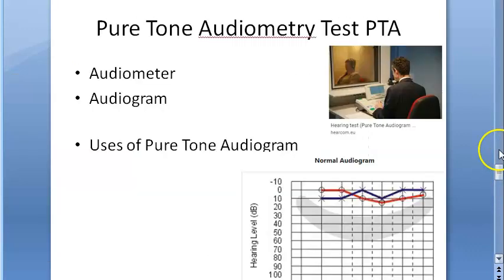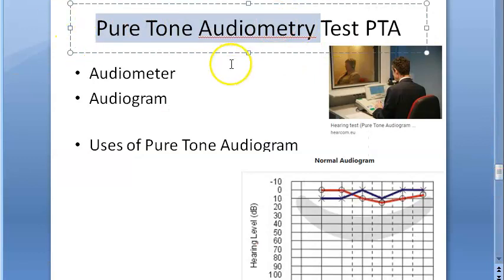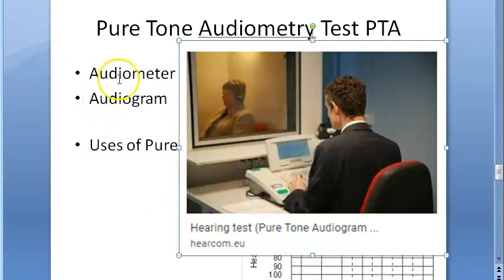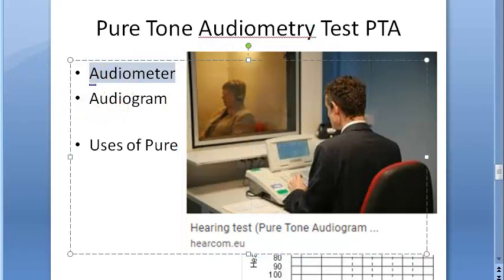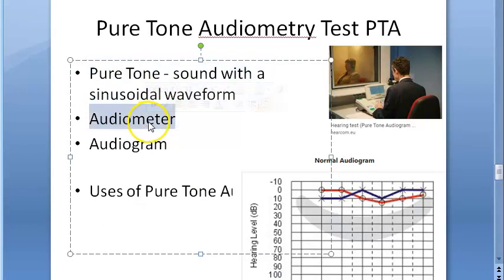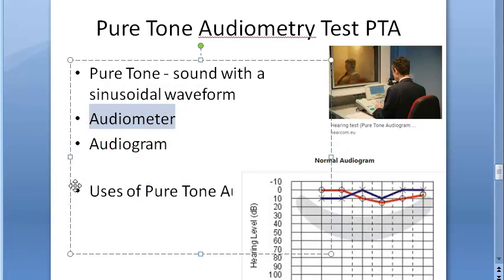Pure tone audiometry is coming under audiometric tests for assessment of hearing. So let us dive into it. An audiometer is an electronic device which produces pure tones. Pure tones means a sound with a sinusoidal waveform. The intensity of these pure tones can be increased or decreased in 5 decibel steps.